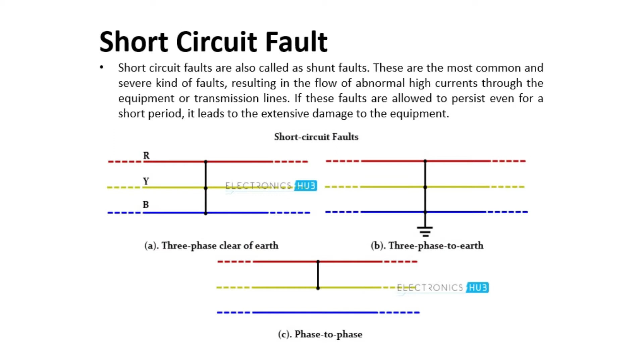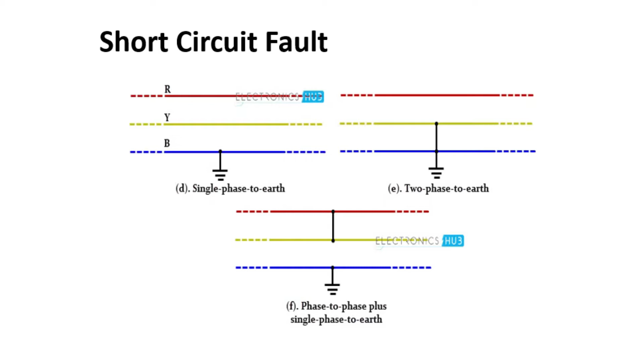They are the most common and severe kind of fault, and they result in the flow of abnormally high currents through the equipment or transmission lines. So students, if these faults are allowed to persist even for a short period of time, it leads to extensive damage to the equipment. The possible short circuit fault conditions include, as you can see here, three phase clear of earth, three phase to earth, and phase to phase fault. The other types can be single phase to earth, two phase to earth, and phase to phase plus single phase to earth. So there are 6 different types of these faults.